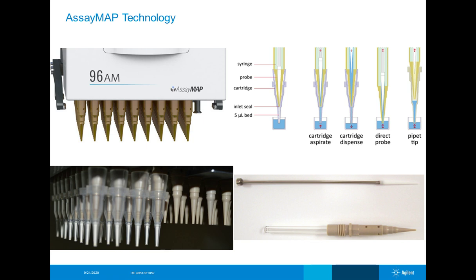In the lower right-hand corner you see what the syringe looks like. The beige part is chemical-resistant PEEK plastic with high-quality chemical-resistant glass at the top, and the syringe plunger has a Teflon coating at the very end. There's one piston inside the head moving all 96 syringes at once, so they're not independently controlled — but because reagents are arranged in columns in our reagent plates or cartridges on the head, we can do different numbers other than the full 96 all at once.